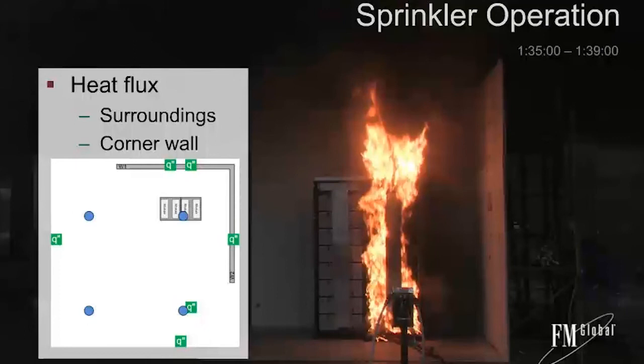The reason I make these measurements is really two goals in sprinkler protection. The first one is to control or suppress the fire. That means to take the amount of energy the fire is producing, you need to make sure it doesn't get any worse, or try to actively reduce that amount of energy. The other thing you can do is protect the surroundings. That's why we have such a high density of these heat flux gauges at different locations. And the manner that we did this allows me to adjust my measurement. Say I make a measurement where the heat flux gauge is 10 feet away, but I'm interested in what the heat flux would have been 3 feet away. With the way we've made these measurements, I'm able to make that adjustment and come up with some reasonable estimates.